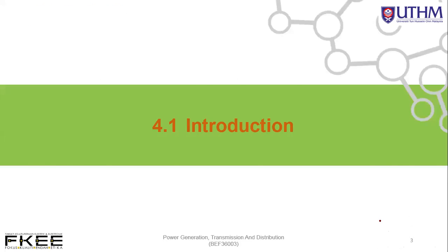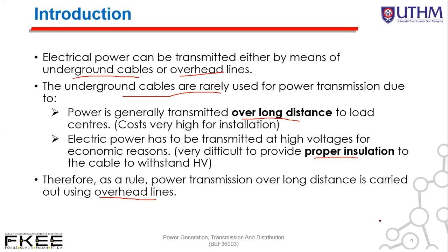Basically, as an introduction, we would like to know that electrical power can be transmitted either by means of underground cable or overhead lines. Underground cables are rarely used for power transmission because power is generally transmitted over long distance to load center, so this will generate very high cost for installation. Secondly, electrical power has to be transmitted at high voltage for economic reason. Because of that, it is very difficult to provide proper insulation to the cable to withstand the high voltage. Because of that, as a rule, power transmission over long distance is carried out using overhead lines.